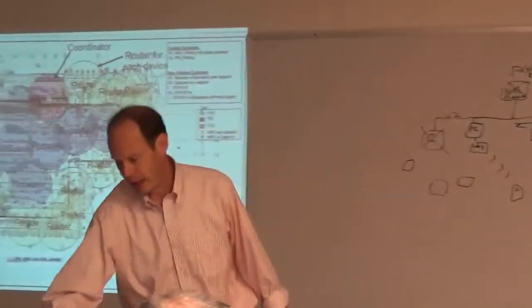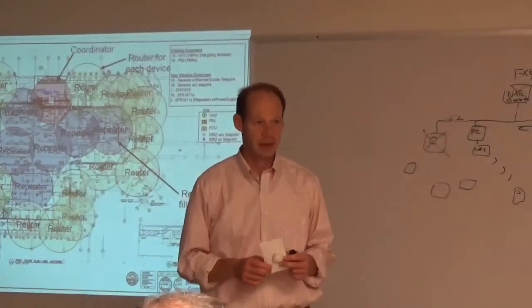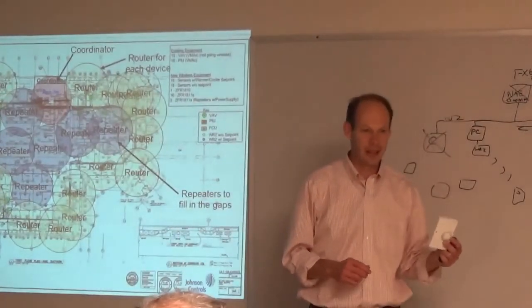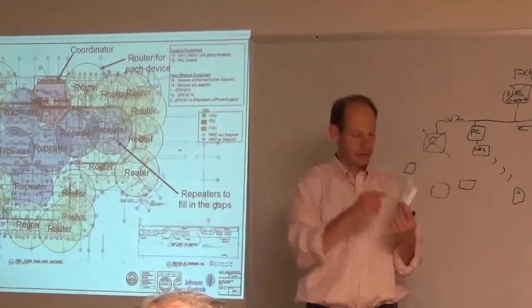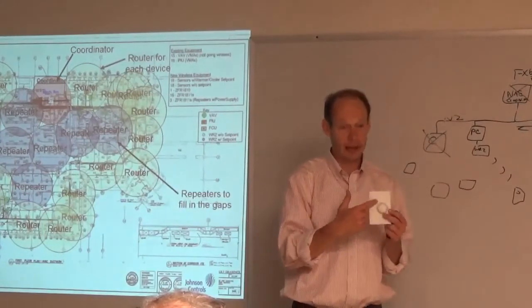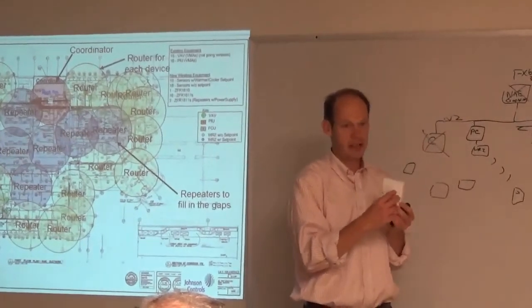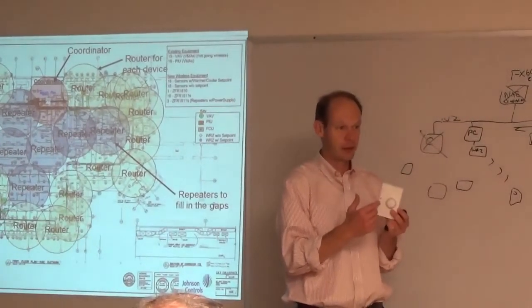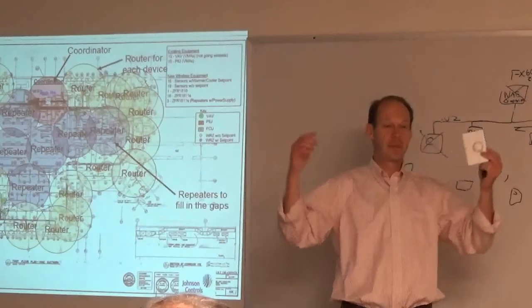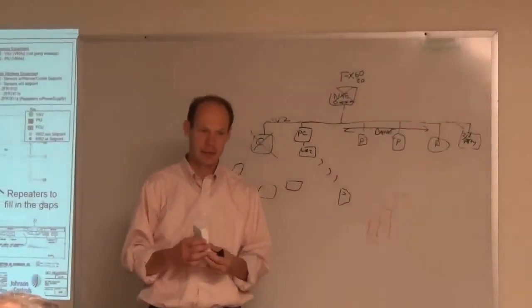The stats with batteries in them communicate every five minutes or so. They wake up, send my value. If you have a display on it, it powers the display all the time, showing my space temperature. If I move the set point adjust or warmer/cooler, that works too. Then it wakes up, sends its value, and goes back to sleep. Whereas the coordinator can power it all the time.